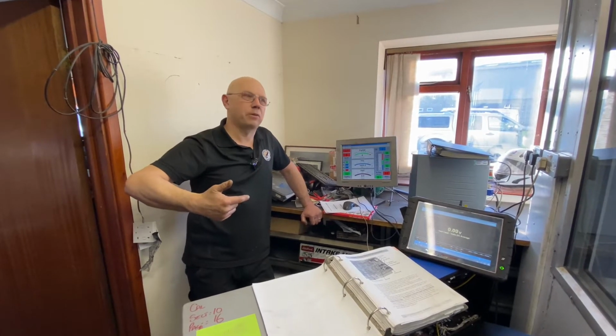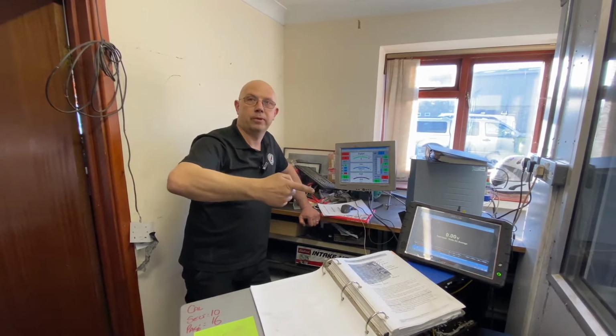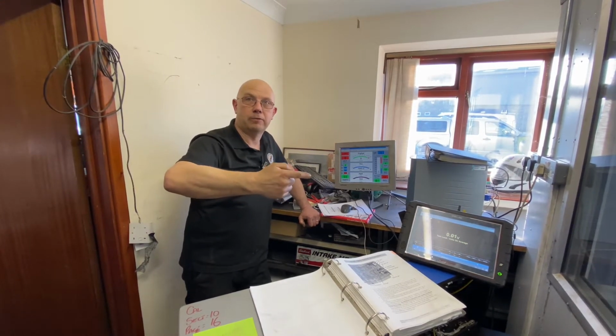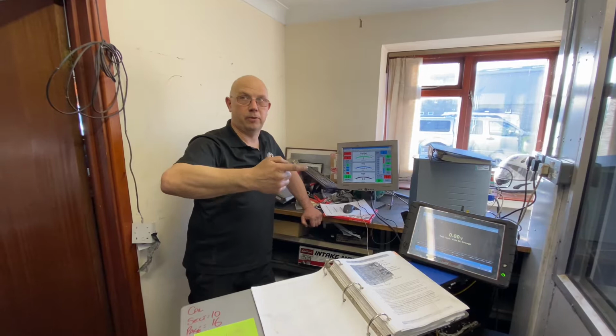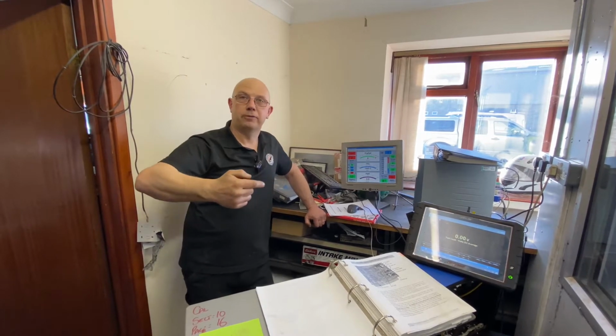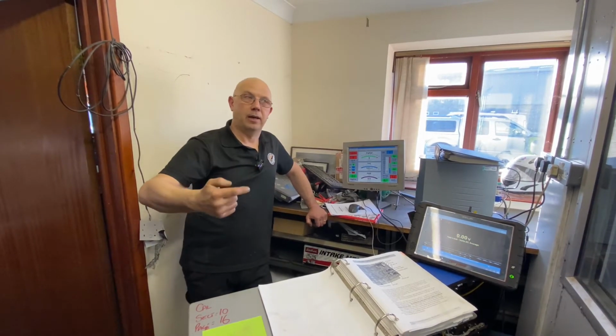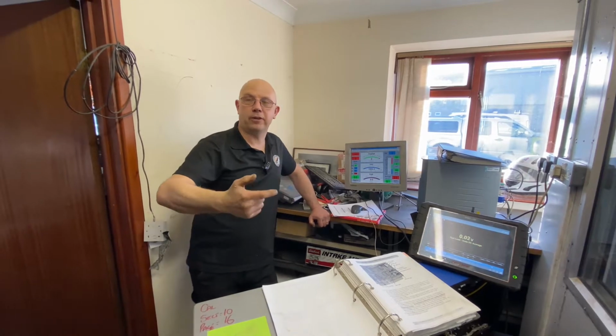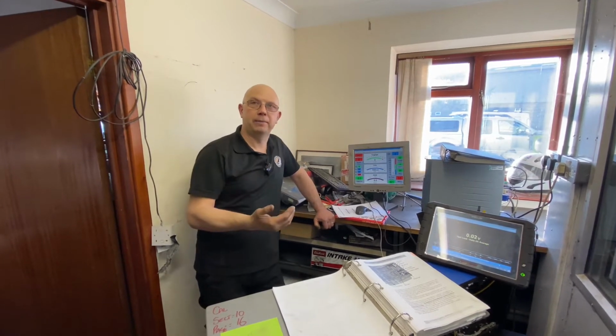Partly down to the fact that we don't technically have the correct calibration arm for this power absorber. We've got an arm for an 833, and we've got the bigger 871, so one arm doesn't fit. The other arm we have got is the correct length, but it's different, because of the way Superflow calibrate them - the calibration arm is a known weight. The arm we've got that does fit has been made differently.